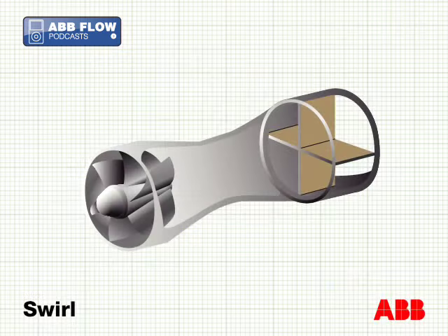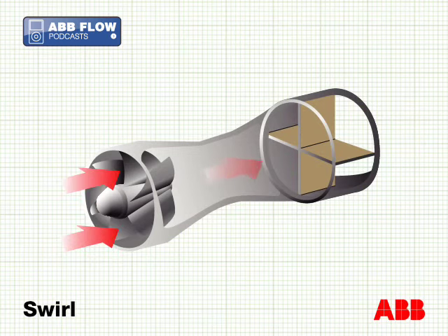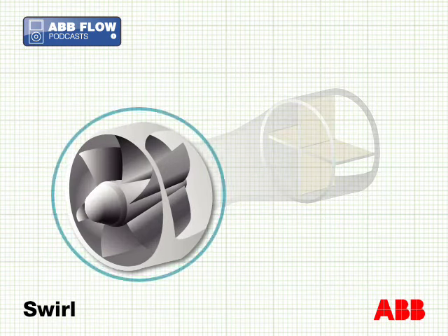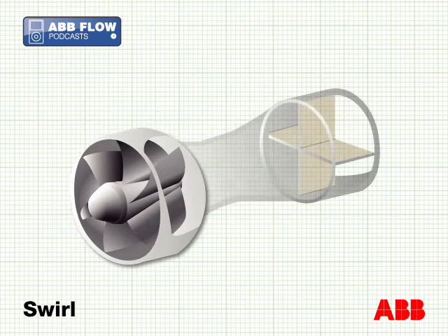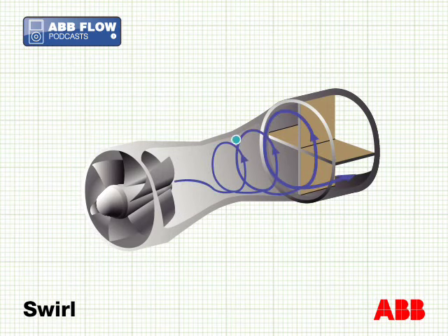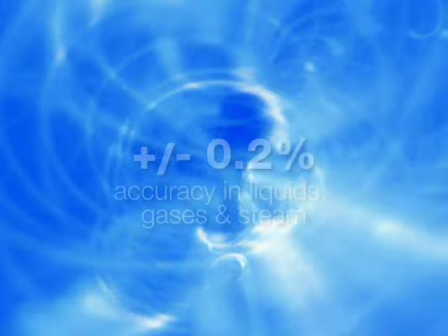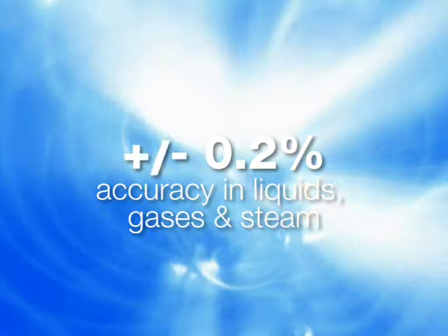The ABB swirl flow meter is based on the pressure variations which occur when a flow is interrupted by an obstruction, similar to the vortex principle. Here the flow passes through fixed spiral vanes. These cause a spiral flow pattern which rotates down the pipe. The frequency of the fluid's rotation is dependent on the flow rate. A sensor detects the speed of rotation and transmits the signal to the electronics. These instruments are also widely used in harsh process and environmental conditions.